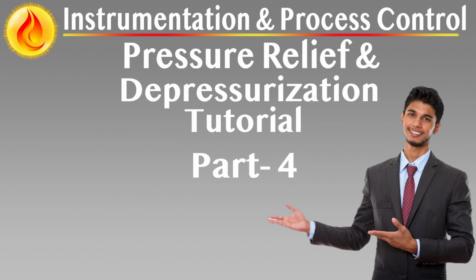Not all relief valves will open simultaneously. Operator intervention and system damping effects reduce peak simultaneity. If two or more units are known to respond simultaneously to a given event, e.g., due to shared cooling or power, their loads must be fully combined for sizing.